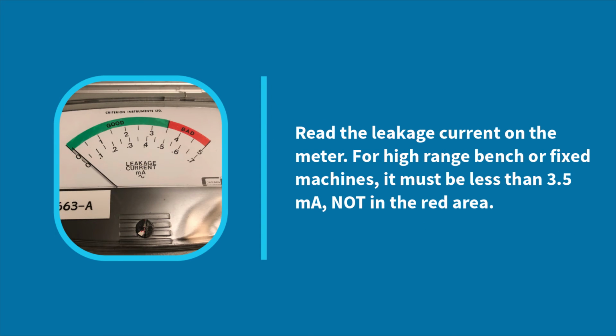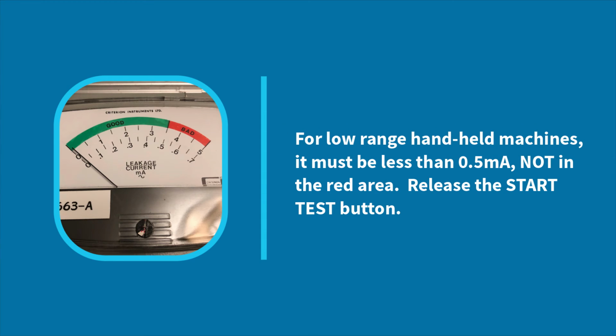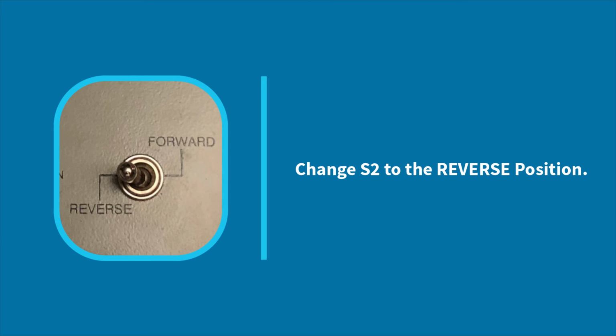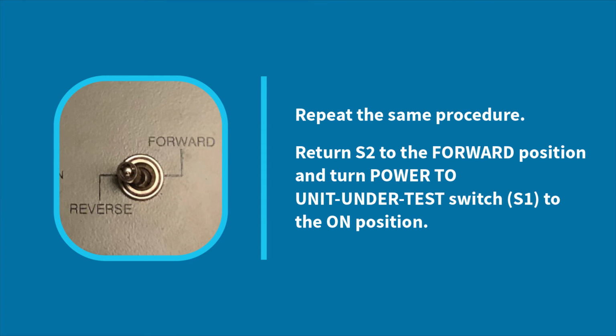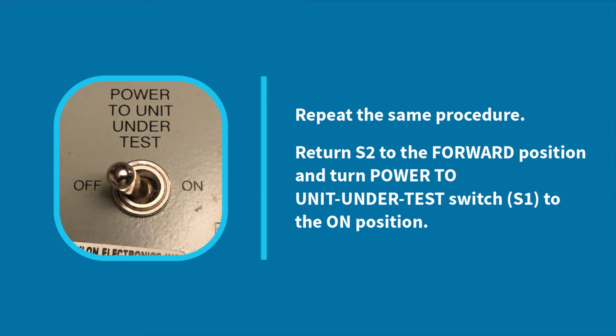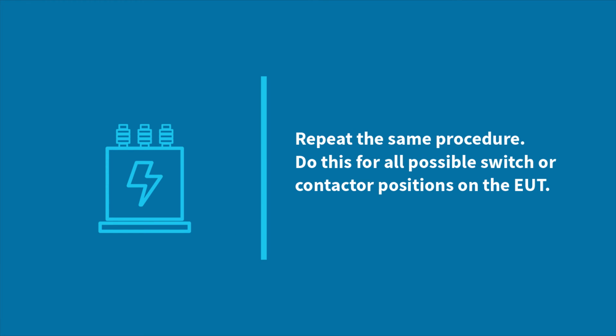Read the leakage current on the meter. For high range, bench, or fixed machines, it must be less than 3.5 milliamps, not in the red area. For low range, handheld machines, it must be less than 0.5 milliamps, not in the red area. Release the Start Test button. Change S2 to the reverse position. Repeat the same procedure. Return S2 to the forward position and turn power to unit under test switch S1 to the on position. Repeat the same procedure. Do this for all possible switch or contactor positions on the EUT.